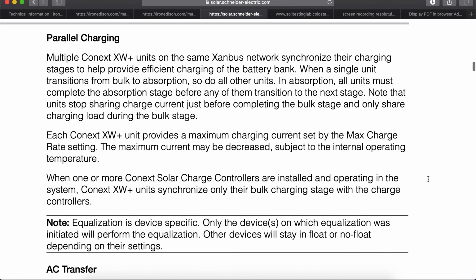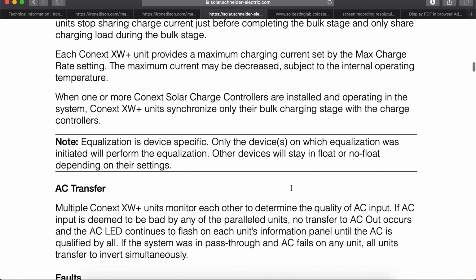When one or more Conext solar charge controllers are installed and operating in the system, Conext XW Plus units synchronize only their bulk charging stage with other charge controllers. Note, lead-acid battery equalization is device-specific. Only the devices on which equalization was initiated will perform the equalization. Other devices will stay in float or no float depending on their settings.